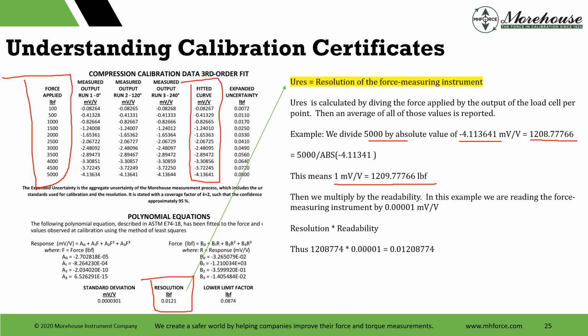Then we multiply by the readability. In this example, we are reading the force measuring instrument by 0.00001 millivolts per volt. If we were reading it by 2 counts, we would multiply by 0.00002. If 5, 0.00005. So here at the bottom, we multiply that and we get 0.01208774, and we round that. Thus, the real resolution of this cell is 0.01208,774. Rounded, it is 0.0121. And if we take the average resolution, we would do this for each force point.